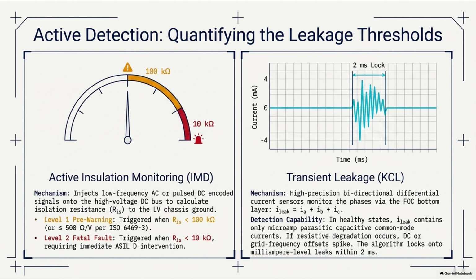Resonant frequency. Let's ground that. Are we talking about vibrations? Electrical vibrations, yes. Imagine the electrical system as a tightly tuned guitar string. Okay. When the plastic insulation is brand new and healthy, those electrical waves vibrate at a very specific expected frequency. Right. But as we discussed earlier, the heat and the sparks are chemically altering that plastic over time. As the polymer degrades, its parasitic capacitance changes. Parasitic capacitance, meaning the plastic's ability to hold an electrical charge is shifting. It's getting chemically spongy before it actually cracks.